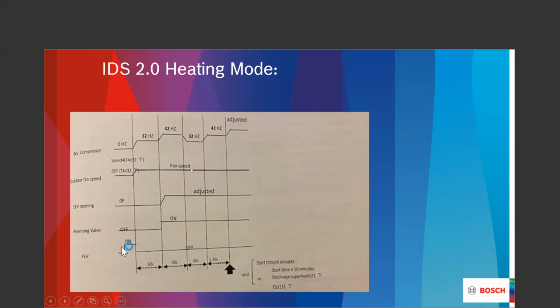This particular stage right here, now we're remembering what we did last hour. Now what we're doing here is, can we do what we did last hour at this point in time? Can we do it with the same hertz that we're at right now? And then we do that for 90 seconds, and then we go back up to the 42 for another 30 seconds, and then we now can be adjusted to whatever we're looking for. That degree of temperature, that 107 or that 114 number that we chose on SW44, that's what our target would be.